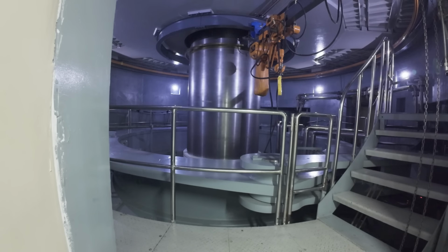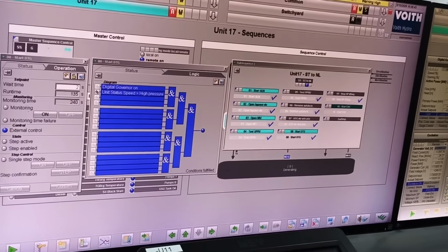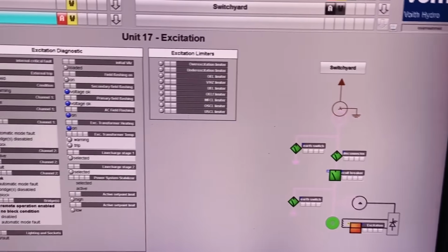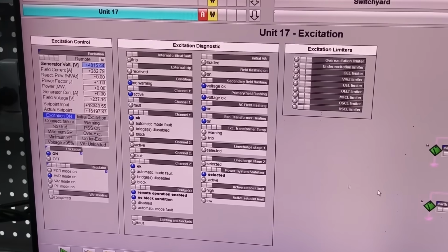Once this stable oil layer forms, the control system automatically shuts down the high pressure lifting pumps because they are no longer needed. And this is a major milestone during startup. It confirms the machine has reached stable rotational behavior. Then step number 10 is the excitation and no load operation.